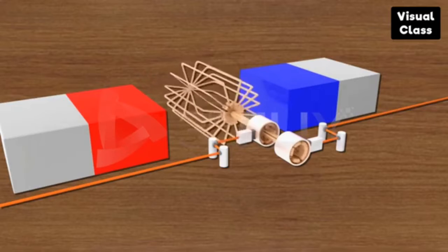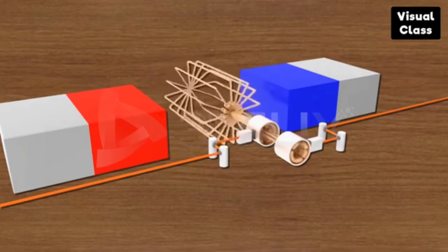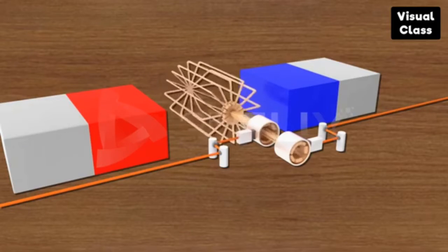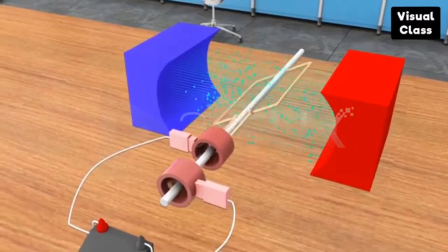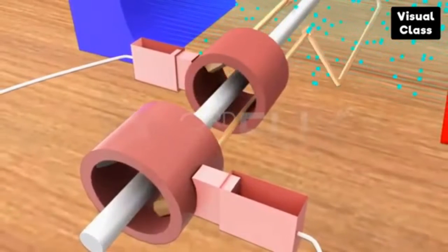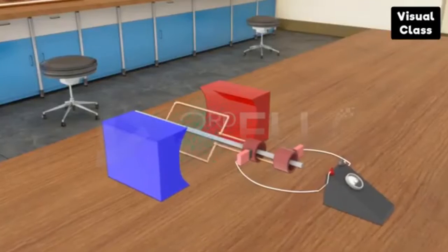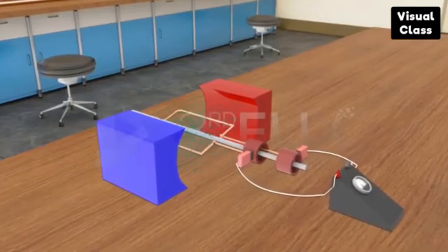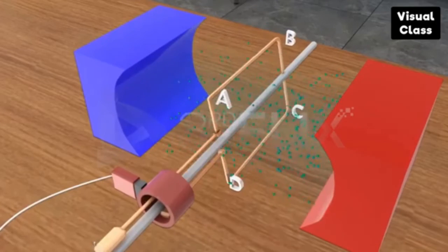The bearings support the rotor. They maintain the air gap and transfer the shaft load to the motor casing. The rotor core and winding assembly is mounted over the shaft. Additional products to protect the motor winding from short circuits, such as combination paper, rubber, varnish, and glass fiber, are used as insulators.